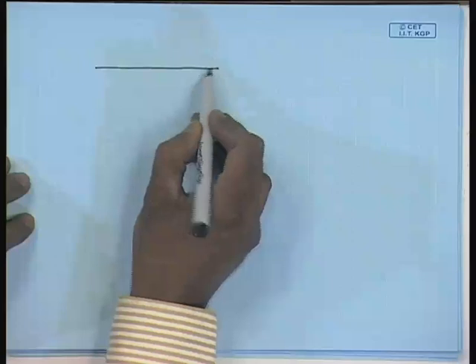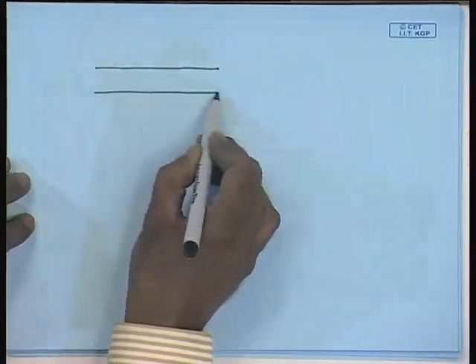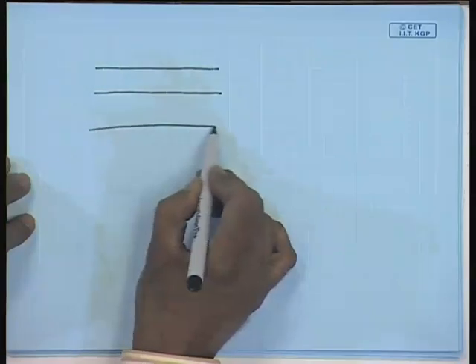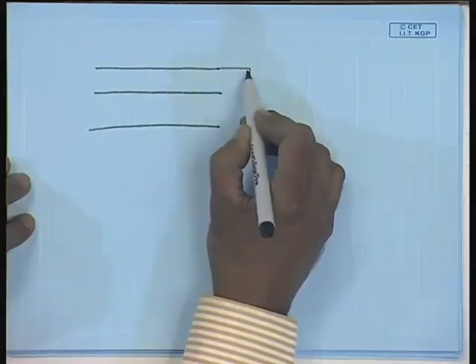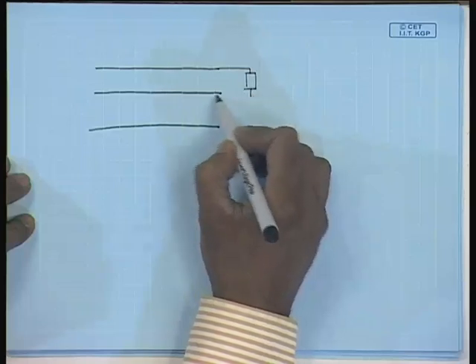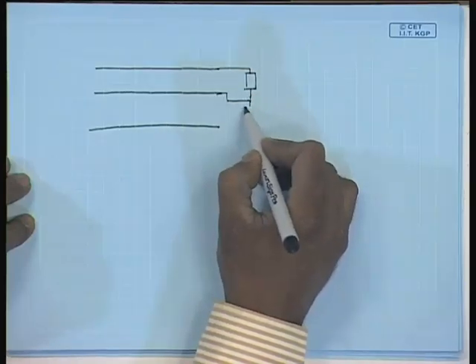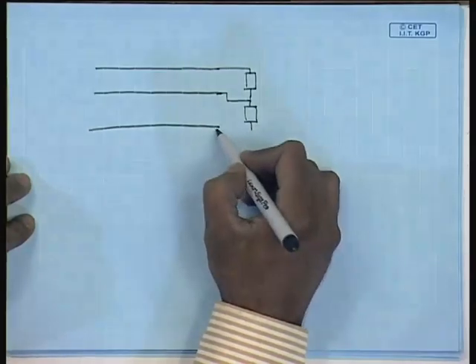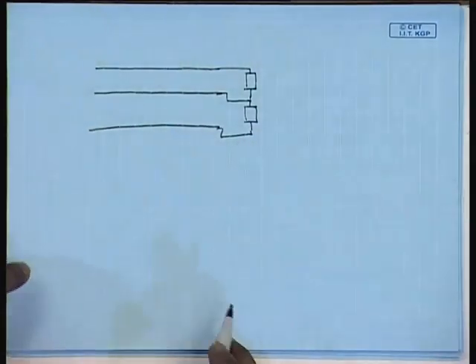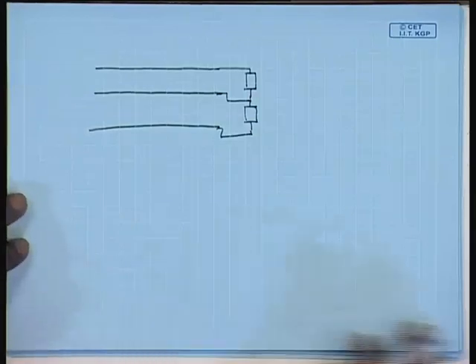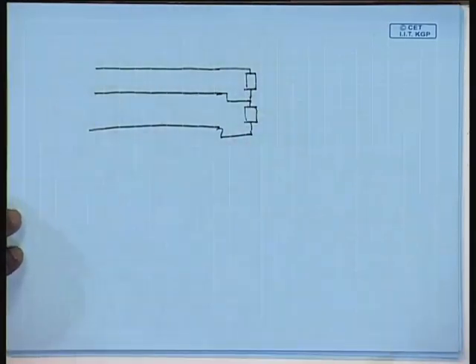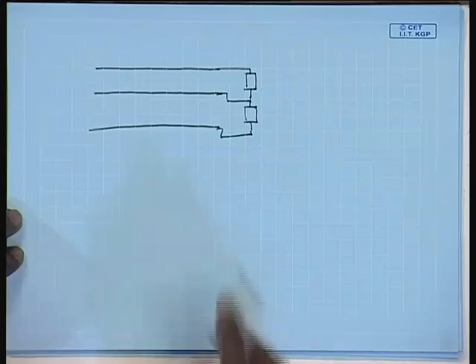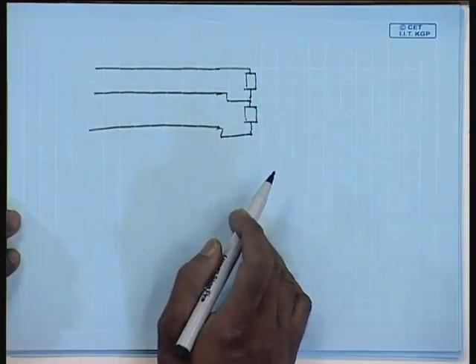In many situations, it becomes necessary to supply a balanced or unbalanced two phase or single phase load from a balanced three phase supply. One way to do this for a two phase load is to connect the two phases between two lines. This is one possibility; however, even when these phases are balanced, impedances are balanced, they will draw unbalanced current from the supply.